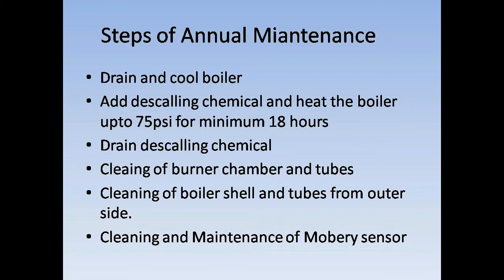First of all we have to drain the water and cool our boiler. Then we have to add the descaling chemical according to the chemical engineer's criteria. We have to heat the boiler up to 75 psi for a minimum of 18 hours. When the descaling chemical has been heated for 18 hours, we then have to drain the descaling chemical.